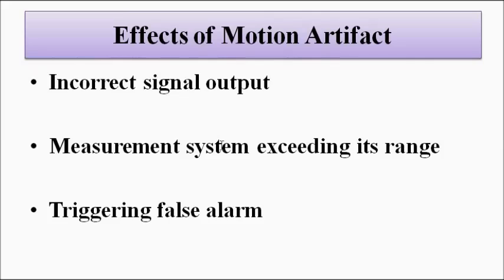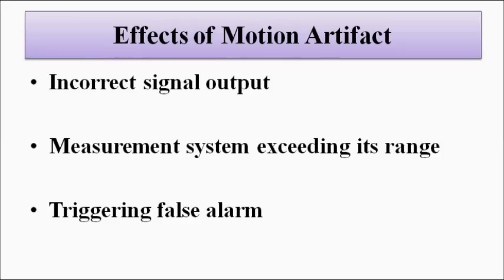The effects of these undesired artifact signals include: first, the signal output will be incorrect, as artifact signals mix with the original signal and cause a reduction or increase from the true value. Second, the measurement system may exceed its maximum range, which can trigger false alarms. Third, baseline wandering can occur. There are various problems associated with motion artifacts due to patient body movement.